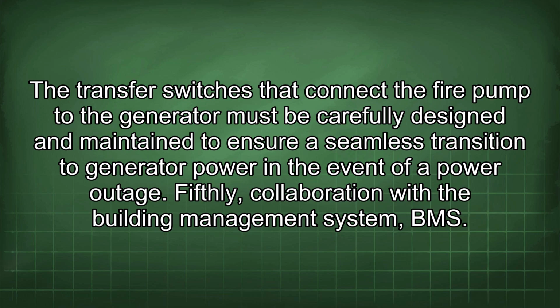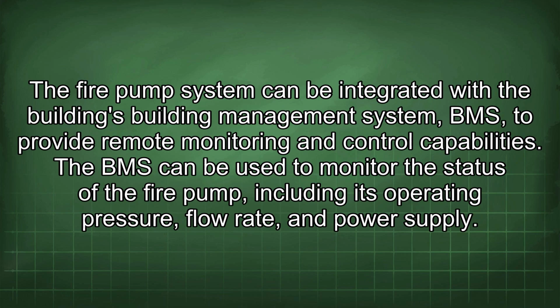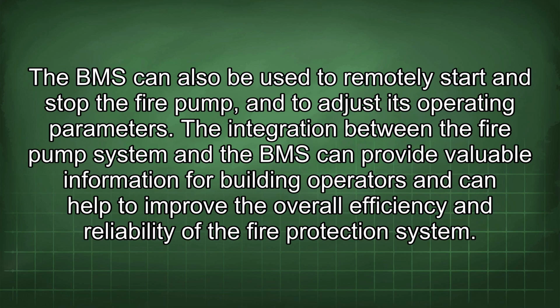Fifthly, collaboration with the building management system (BMS). The fire pump system can be integrated with the building's building management system (BMS) to provide remote monitoring and control capabilities. The BMS can be used to monitor the status of the fire pump, including its operating pressure, flow rate, and power supply. The BMS can also be used to remotely start and stop the fire pump and to adjust its operating parameters. The integration between the fire pump system and the BMS can provide valuable information for building operators and can help to improve the overall efficiency and reliability of the fire protection system.